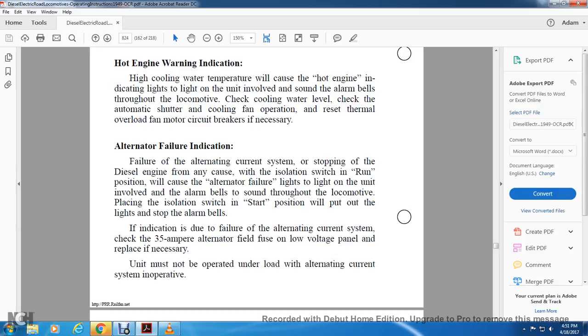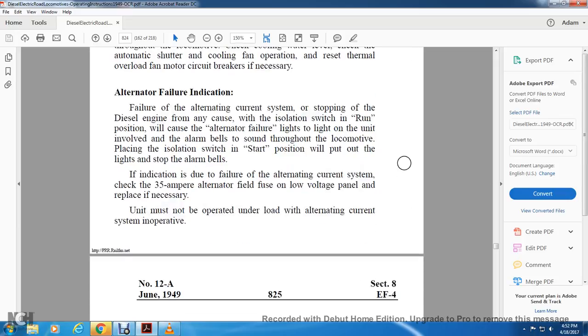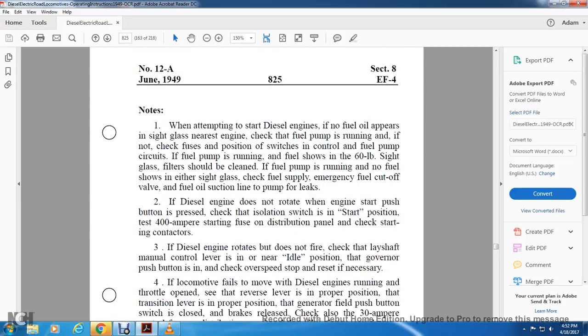If the indication is due to failure of the alternating current system, check the 35 ampere alternator field fuse on the low voltage panel and replace as necessary. Units must not be operated with the alternating current system inoperative. Note: when attempting to start the diesel engine, if no fuel appears in the sight glass nearest the engine, check whether the fuel pump is running.